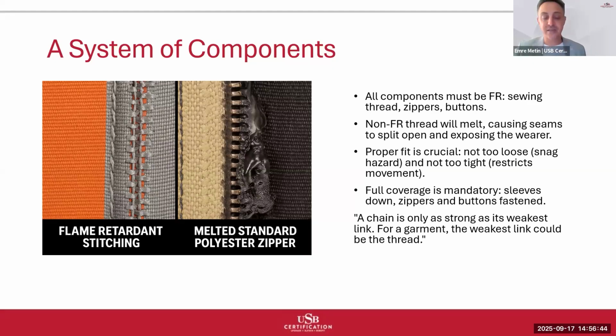The key insight: think of arc-rated PPE as an engineering protection system where every component must function correctly for the system to provide its rated protection level. Just as you wouldn't use regular bolts in a high-pressure piping system, you can't use regular components in arc-rated clothing and expect the same protection performance.